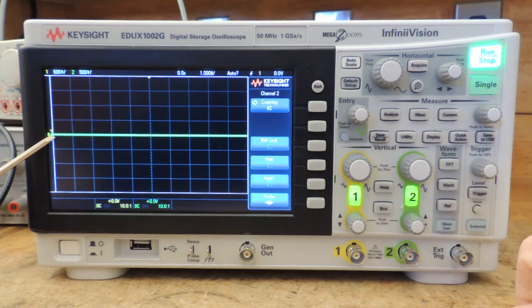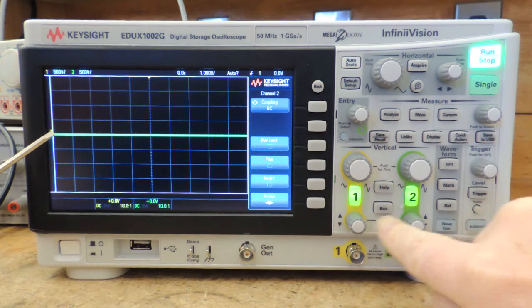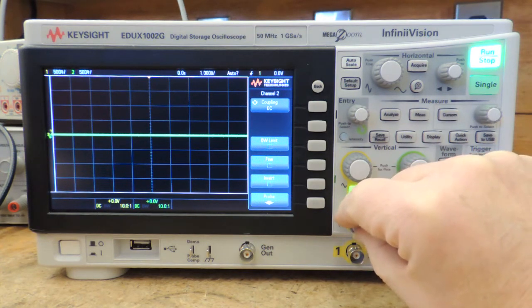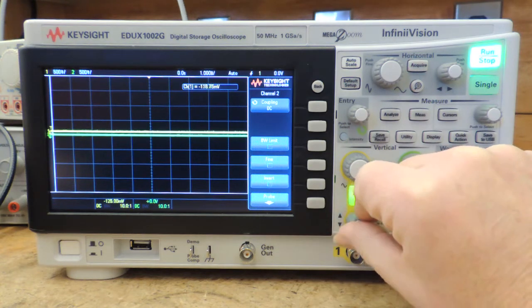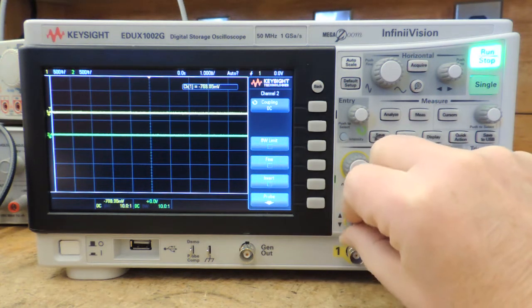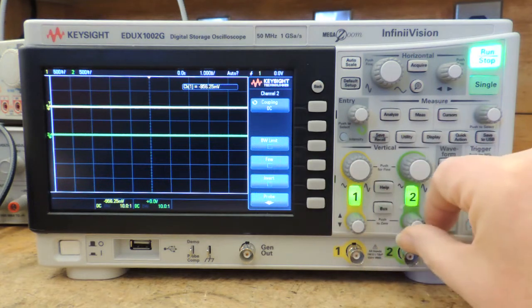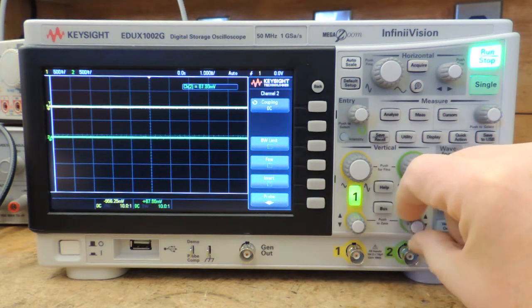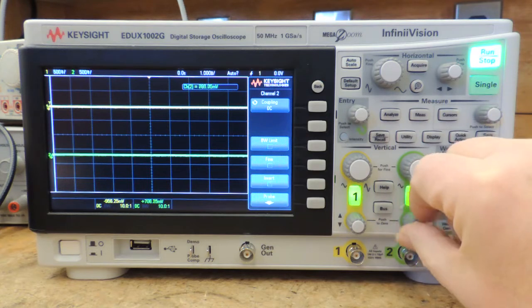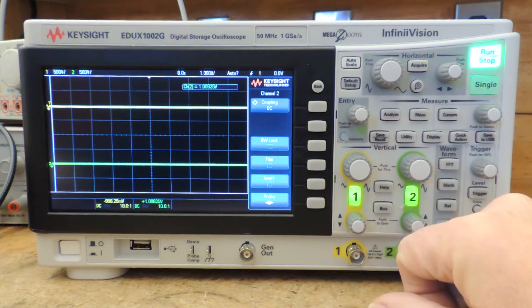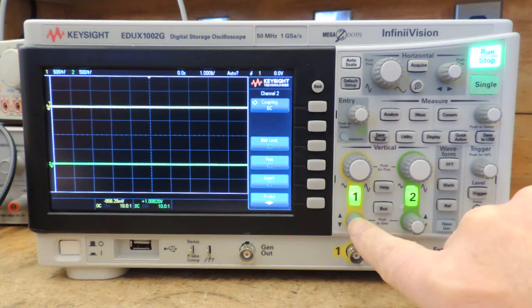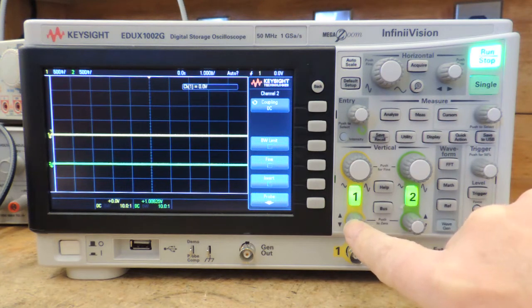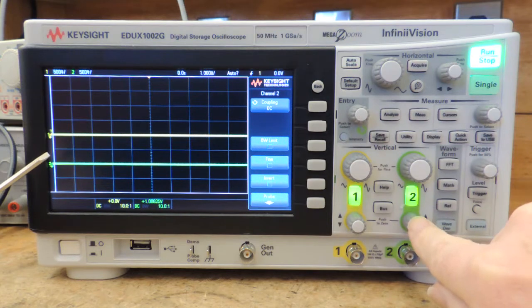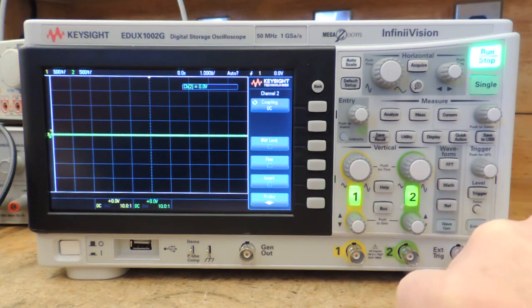The traces on the screen can be moved, so we have some positioning knobs for channel 1 and channel 2. So if I rotate the positioning knob for channel 1, you can see I can move the trace upwards. If I rotate it the opposite direction, I can move the trace down for channel 2. If I want to move them quickly to the zero line, I can just press the center of the positioning knob and it drops it down to the zero line, or back up to the zero line.